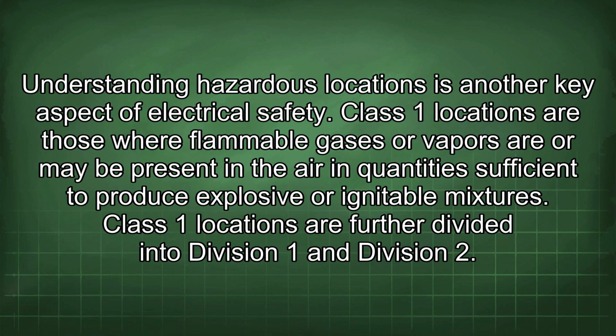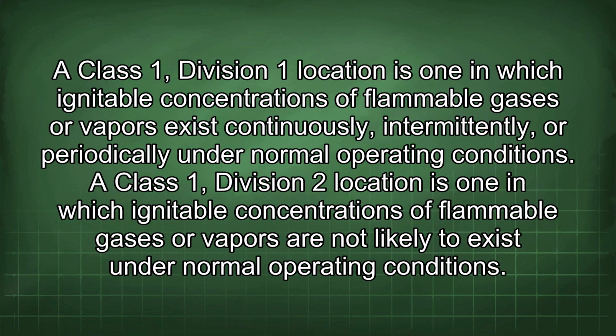Understanding hazardous locations is another key aspect of electrical safety. Class 1 locations are those where flammable gases or vapors are or may be present in the air in quantities sufficient to produce explosive or ignitable mixtures. Class 1 locations are further divided into Division 1 and Division 2. A Class 1, Division 1 location is one in which ignitable concentrations of flammable gases or vapors exist continuously, intermittently, or periodically under normal operating conditions.